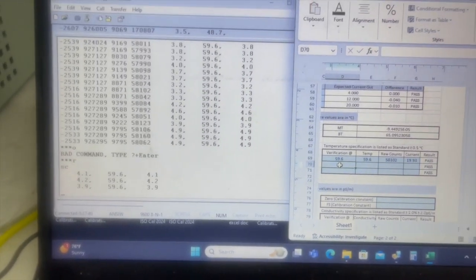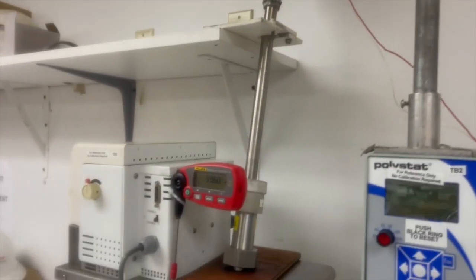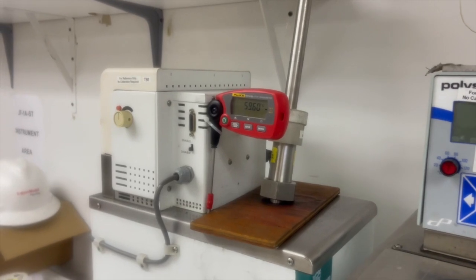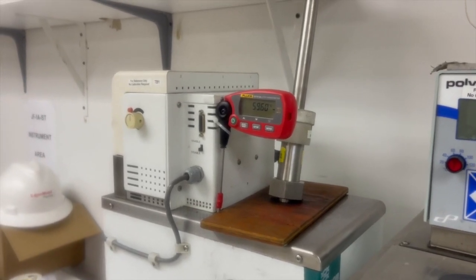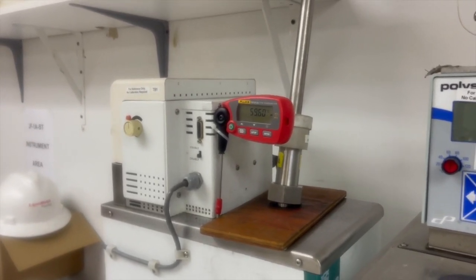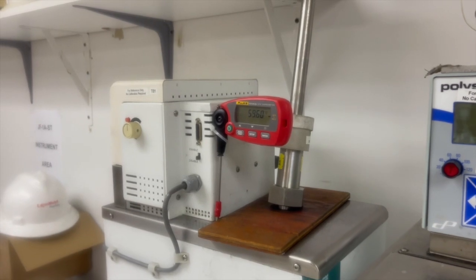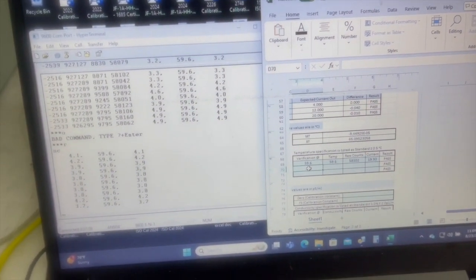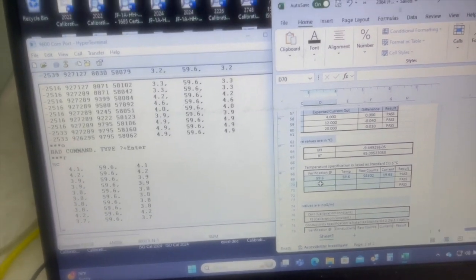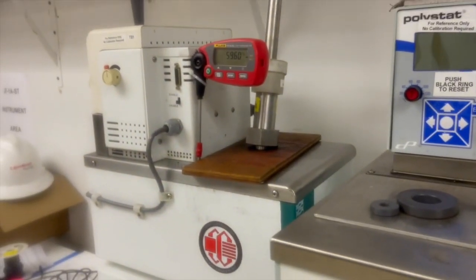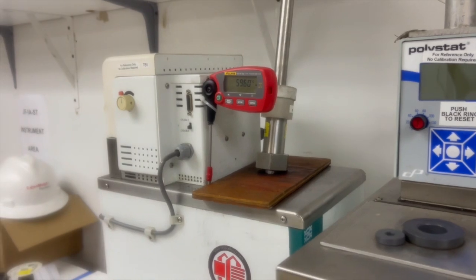So then we move on to the middle range, which means we have to take the sensor out of the bath and set the temp to 26 degrees and then soak the inline sensor for 30 minutes at 26 degrees and then come over here and fill out this middle section again to see if it verifies the temp at the middle range. And then we'll check the 0 again at 1 degree. So that's what we're doing.